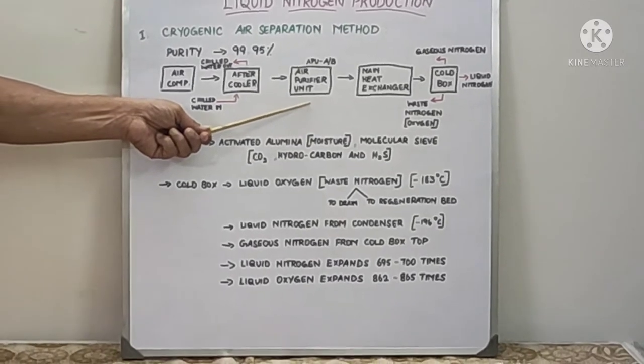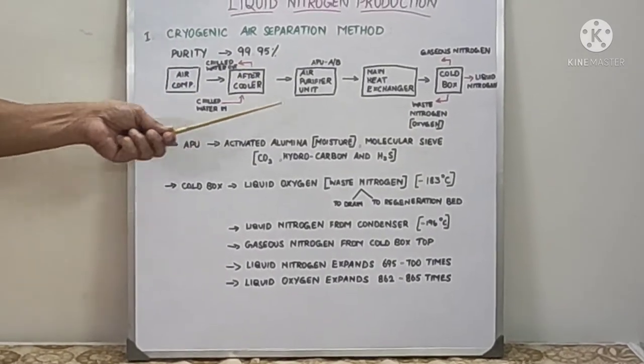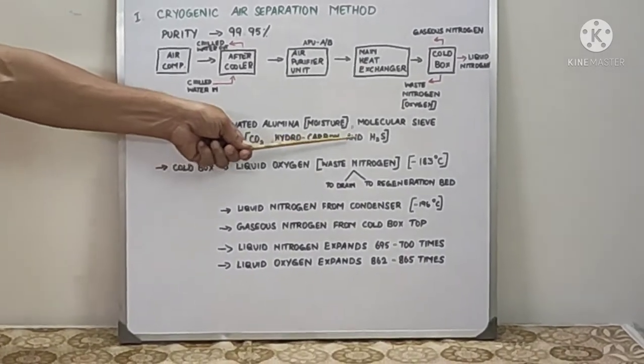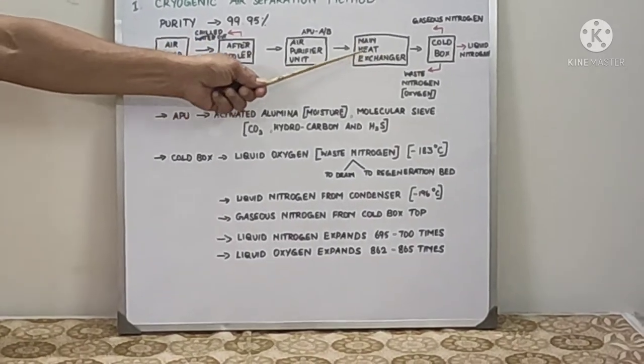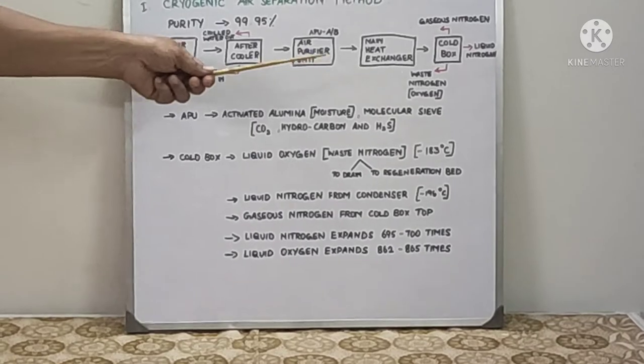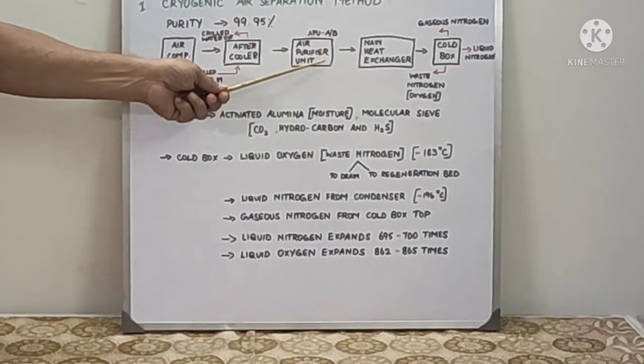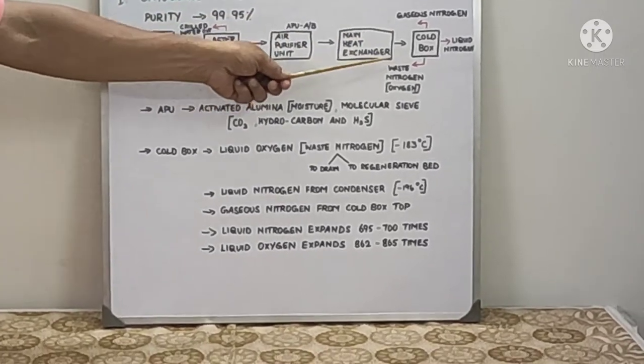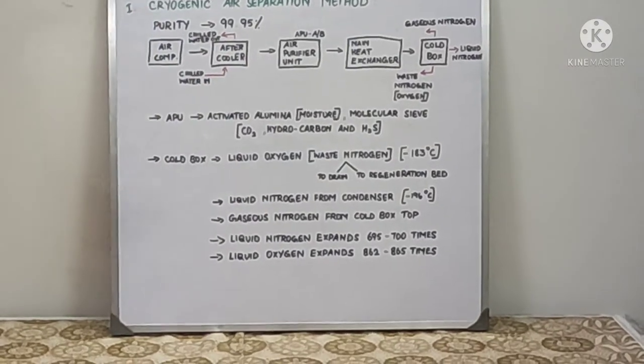For four or five hours heating, then another four hours cooling, then it will be ready for service. The air purifier unit removes CO2, water, hydrocarbons, and hydrogen sulfide. It goes to the cold box through heat exchanger. This main heat exchanger plays a vital role, getting inlet from air purifier as well as from cold box, and outlet going to the cold box and back to the receiver.